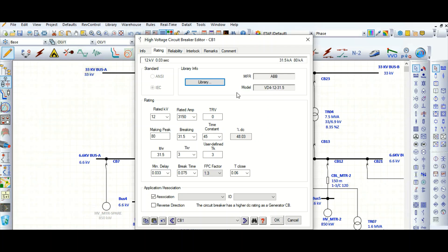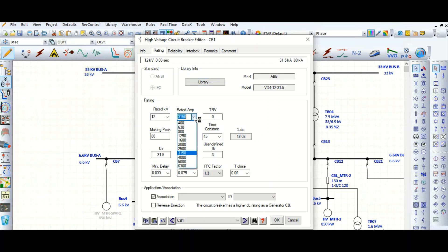This is the ABB model circuit breaker with its model number. The rating is the rated kV — which is 12 kV — and the rated ampere, which is 3150 A, selectable from a drop-down list. Here is the making peak current: when the circuit breaker makes the circuit again after fault clearing, it must have withstand capability.